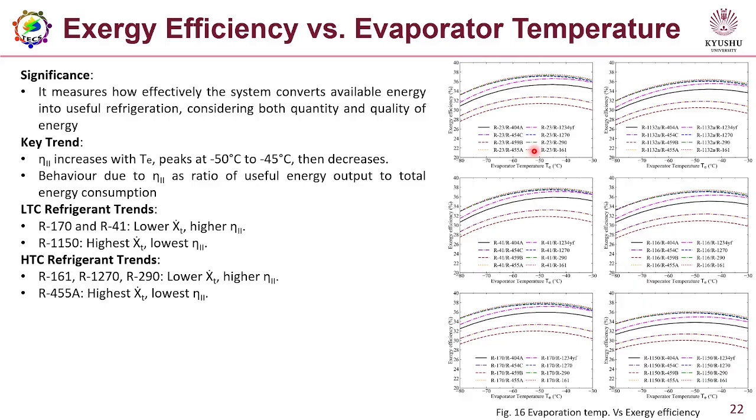So for the refrigerant comparison, the results were the same: the natural and pure refrigerants are performing better than their counterpart HFC refrigerants.